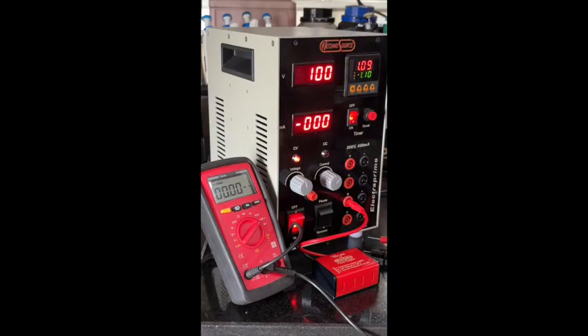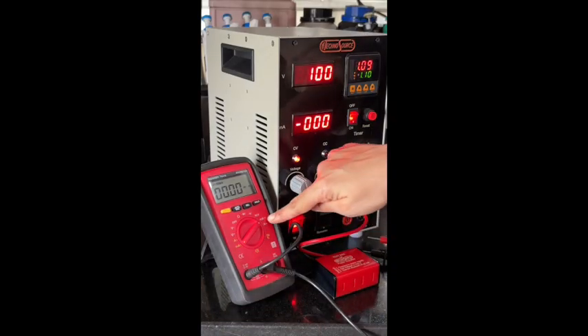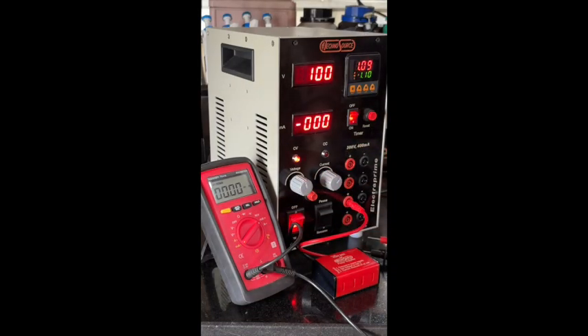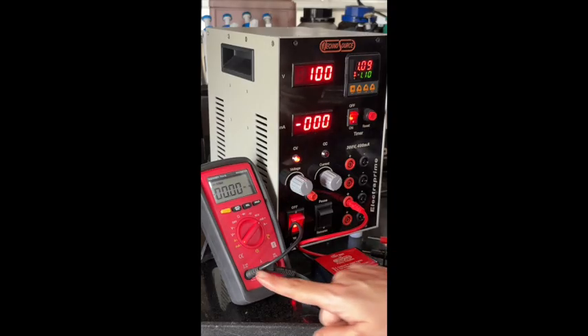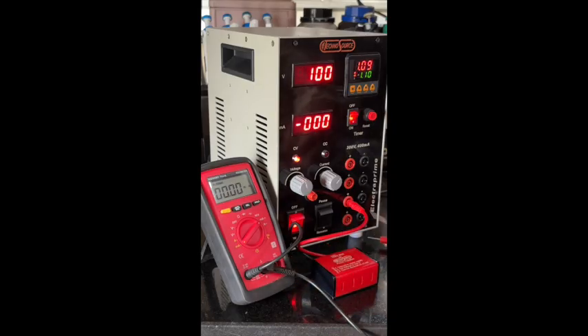Checking the current. Set multimeter to read mA. Connect the power supply to the test box as shown here. Red connector from test box to power supply red terminal. Black connector from the test box goes to the multimeter red terminal. The multimeter black terminal goes to the power supply black terminal. And you'll see the mA should match.